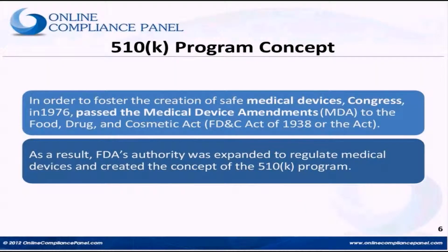Now, let's talk about the 510K program concept. Back in 1976, the Congress passed the Medical Device Amendment, enacted in order to foster the creation of safe medical devices. It is an amendment to the FD&C Act, by the way. As a result, FDA authority was expanded to regulate medical devices, and the FDA created the concept of the 510K program.